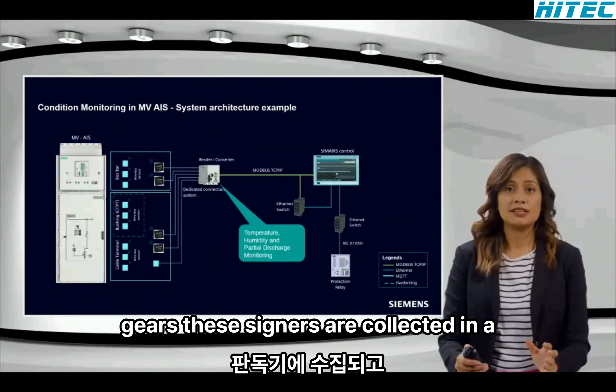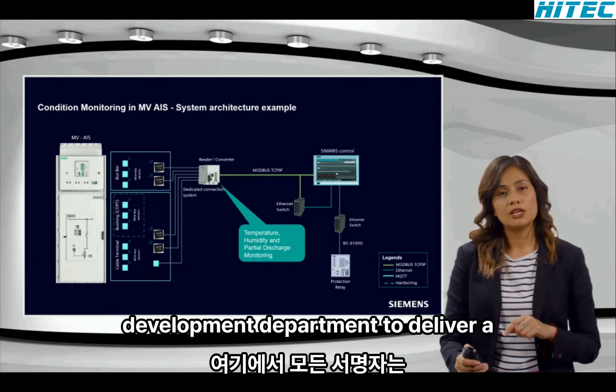Condition monitoring for medium voltage switchgears consists of adding temperature and partial discharge sensors to the switchgear at the bus bar and cable terminals, and also, if requested, in the bushing for NX-Air switchgears. These signals are collected in a reader, and this information, together with the SIPROTEC 5 relay data, goes into the Simaris Control gateway, where all signals are evaluated with a Siemens engine developed by our research and development department to deliver a health indication.